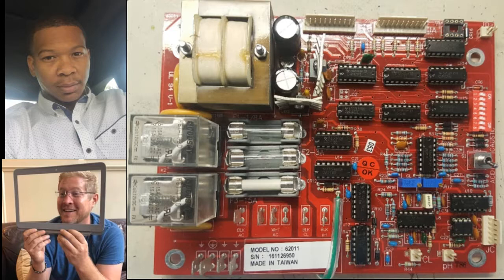Right. And by flipping that switch, you actually calibrate opposite. So if the feed light were on, with acid, you would go clockwise to get it to go off. Now it's just the opposite for caustic. If the feed light is on, you go counterclockwise to get it to go off. So by flipping that switch, it's the complete opposite.